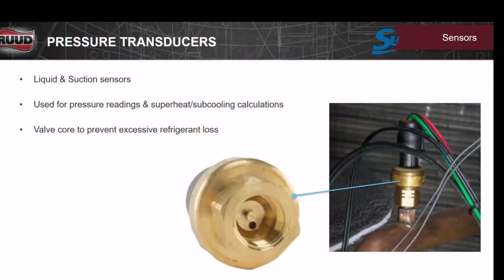This is what a transducer looks like inside. It looks like a pressure switch basically, only with 3 wires. We have common, and then we have our input, our output. So we'll have 5 volts going in and anywhere from 0.4 to 4.5 volts out, depending on the pressure. You can actually tell what your suction pressure is if you have the chart by checking the voltage. It's going to get you really close. There's a Schrader valve in here, so you can replace this under pressure.